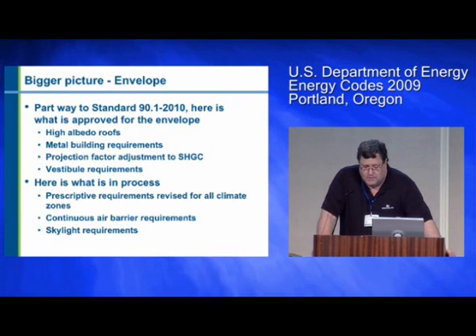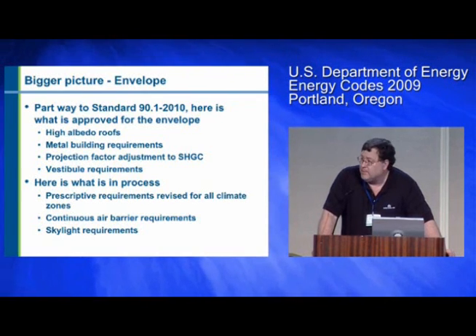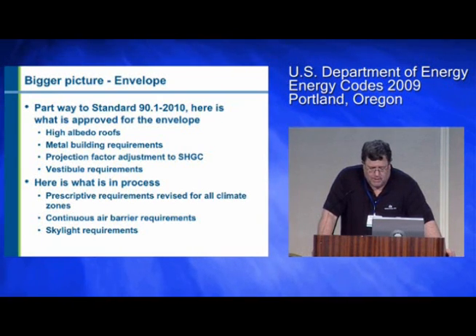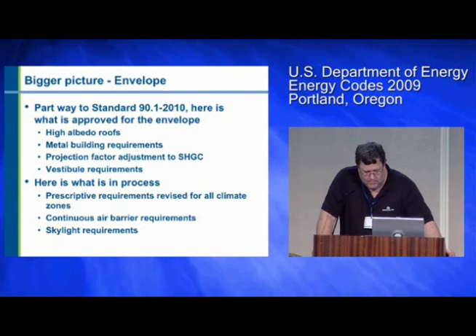So part of the way to standard 90.1 2010 on the envelope, ASHRAE is already going to be requiring high albedo roofs, cool roofs in some climate zones. There are some new metal building requirements in the standard. There are some new adjustments for projection factor and solar heat gain coefficient, and there are new vestibule requirements. But ASHRAE is also working on a whole bunch of other stuff as well. A complete overhaul of the building envelope requirements has been going on for the last year and a half or so. There are going to be a lot of new envelope requirements. For the most part, they're going to be a lot more stringent than what you've seen before.